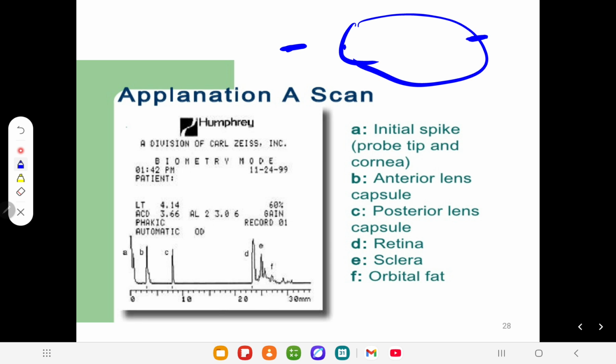Because you want distance from cornea to macula, not cornea to optic nerve. Why? Because in optic nerve, you are not measuring distance to optic nerve. You are basically measuring distance from cornea to macula, isn't it? You want visual axis, isn't it? Yes. So it's very important if you hit optic nerve head, then one thing is very beautiful happens there.